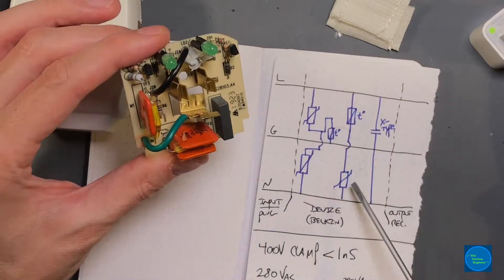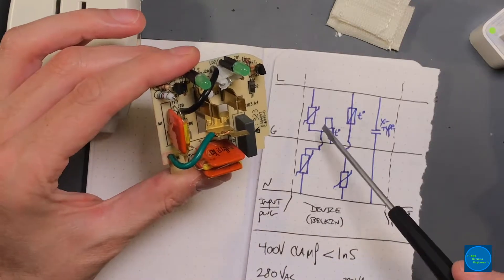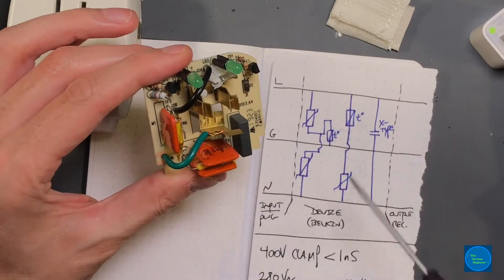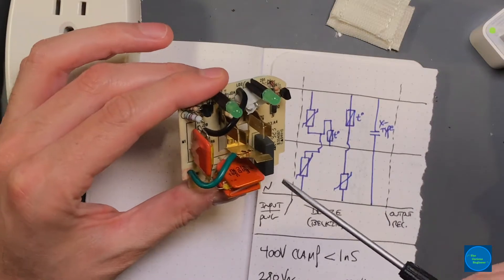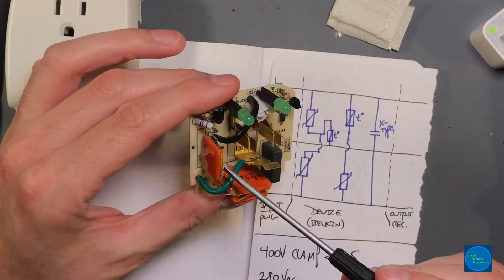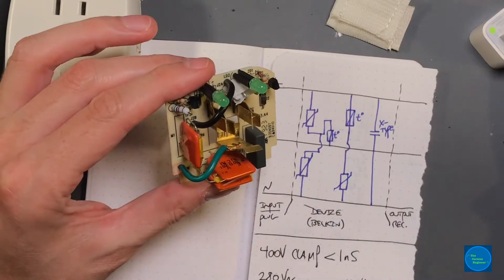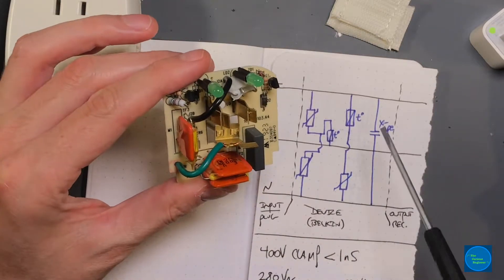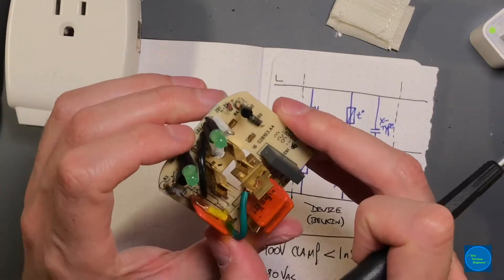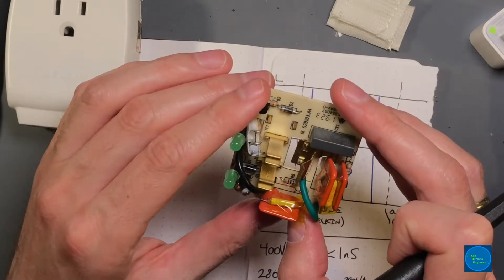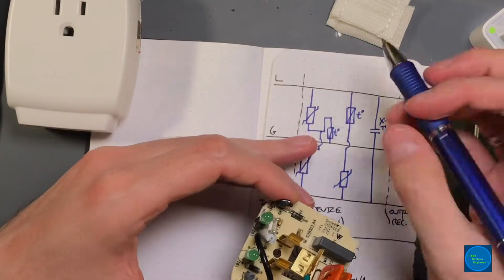That is in the event of any sort of fault where the MOVs fail. The known failure mode of MOVs is short, so they'll fail short. And always before that happens, they get very hot because their impedance drops as they age. But that'll be a topic for a future video. Then the fuses open up. These are rated at 115 degrees Celsius. Basically, that's the operation.